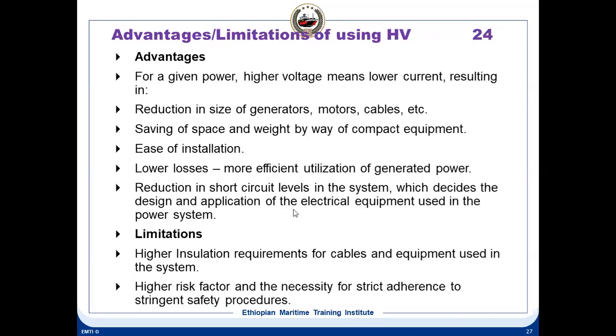What are the advantages of high voltage and what are the limitations? The first advantage is that for a given power, higher voltage means lower current. For a given power, the higher the voltage, the lower the current. Number two, reduction in size of generator, motor and cables. The size is reduced because the current is reduced. So the cable is also reduced.